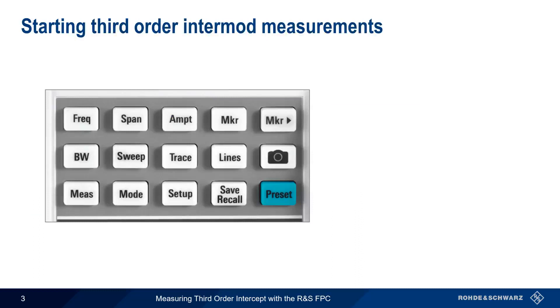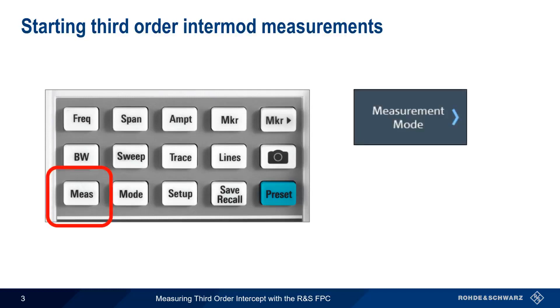On the FPC, third-order intercept measurements are called Third-Order Intermod. To access this measurement, first press the Measure hard key, then press Measure Mode and select Third-Order Intermod.